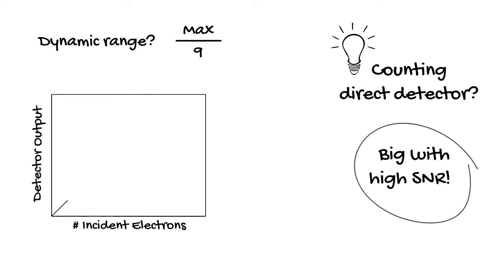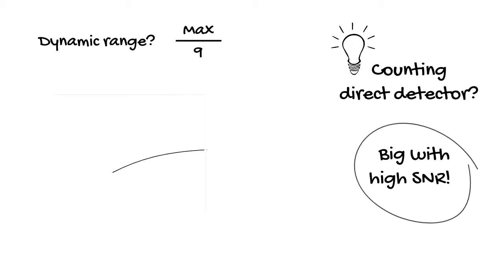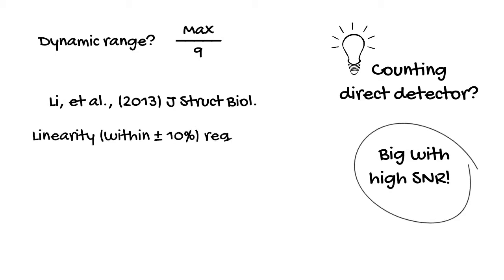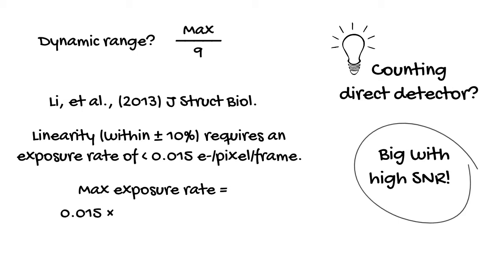Now, how about the maximum? For the EEL spectrum to be interpretable, the detector must be linear. In other words, the signal detected in each channel must be proportional to the number of electrons with the energy of that channel. It's known that electron-counting direct detectors lose linearity as the exposure rate increases. Some manufacturers actually give this away by calling their integrating mode linear mode, in contrast to counting mode. Figures from Li et al. in a 2013 JSB paper showed that linearity within plus or minus 10% requires an exposure rate of no more than 0.015 electrons per pixel per frame. So let's use that as our maximum for counting. Remember, it's certainly possible to acquire images with a brighter beam than that. But the data will quickly lose its utility as linearity is lost.